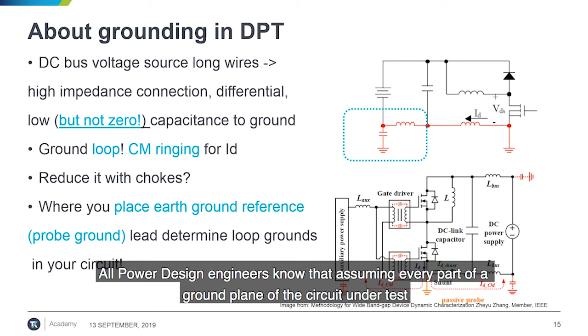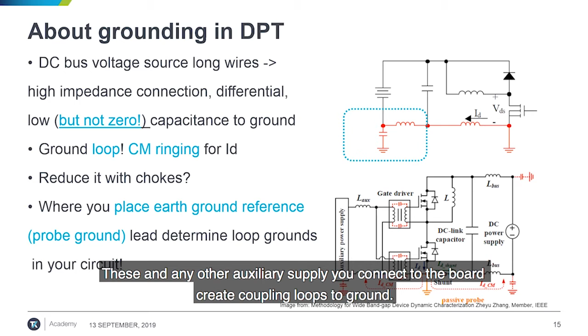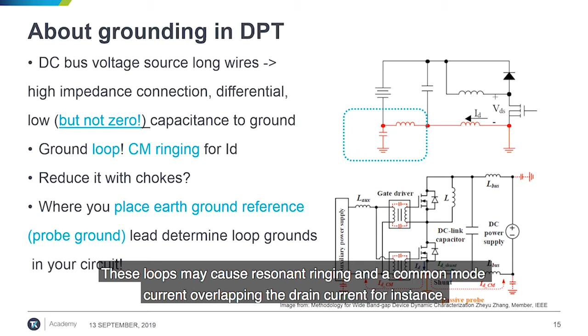So ground reference measurements need to obviously reach ground. Looking at the double pulse test board, there is a ground plane on the board, and all power design engineers know that assuming every part of a ground plane of the circuit under test is actually at the same potential is essentially wrong. So not everything is tied to the same ground in the circuit, same for your measurement system. There are other grounds connected, like the one from the power supplies, for instance, that can reach out to the double pulse test board using long leads, so with parasitic inductances. And this and any other auxiliary power supply that you connect to the board can create coupling loops to ground. So these loops may cause resonant ringing and common mode current overlapping to the drain current, for instance.